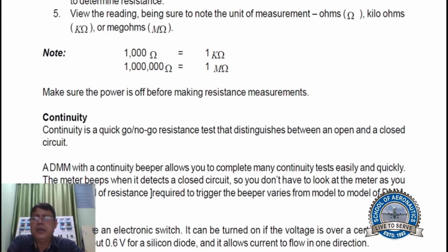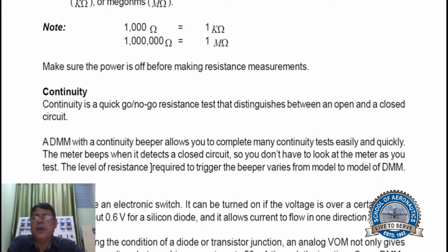Continuity. Continuity is a quick go, no go resistance test that distinguishes between an open and closed circuit. A DMM with a continuity beeper allows you to complete many continuity tests easily and quickly. The meter beeps when it detects a closed circuit, so you don't have to look at the meter as you test. The level of resistance required to trigger the beeper varies from model to model of DMM.